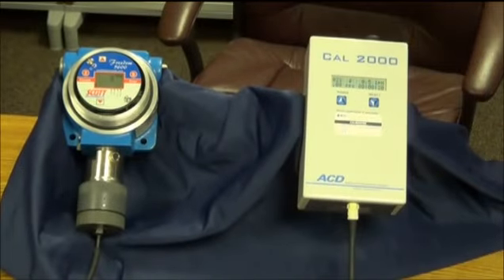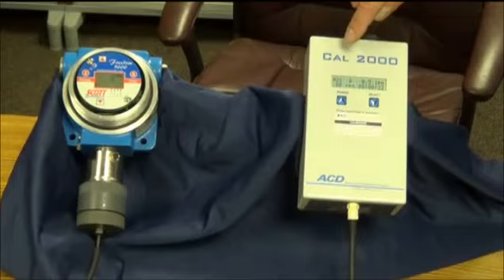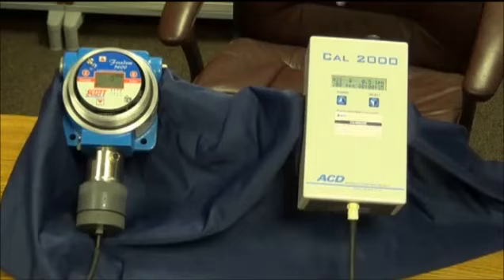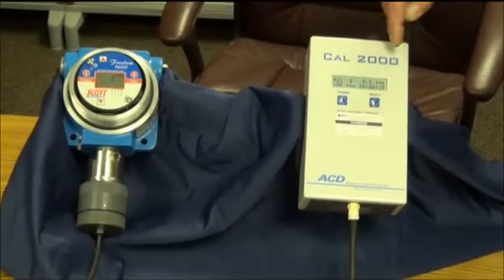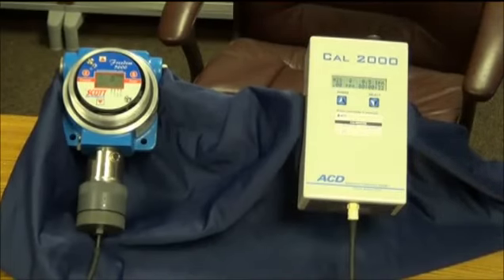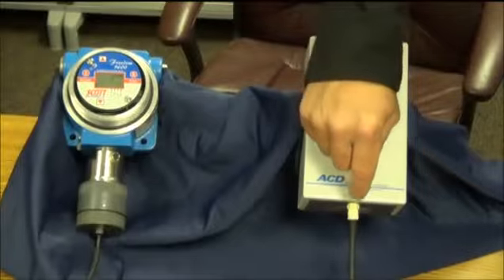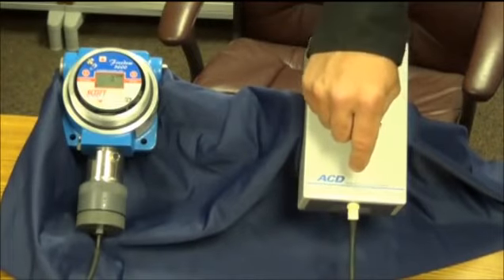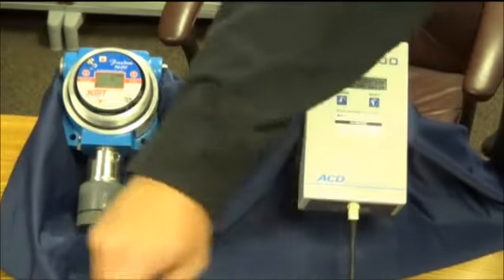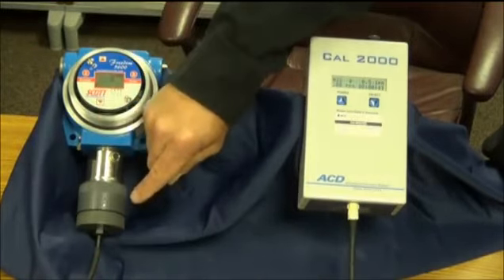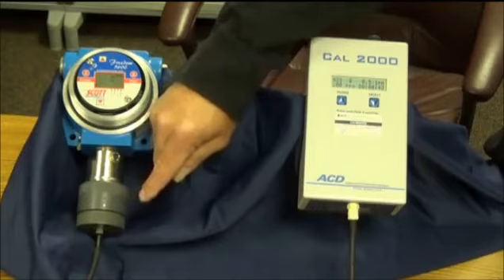Now, as you can see, the Cal 2000 is stabilized at 0 parts per million. So what's happening now is ambient air from the room is coming into the instrument. It goes through a charcoal filter to ensure that if there was any background H2S in this room, it would scrub it out. It's coming out through a 5-foot hose that comes with the Cal 2000, and then it's going into a calibration adapter that came with the Scott sensor.